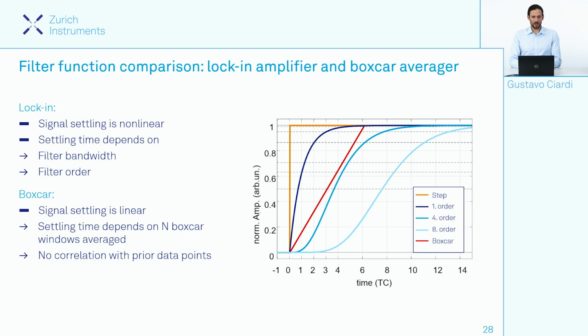Another very interesting and important difference between lock-in amplifiers and Boxcar Averagers is the filter function. For the lock-ins, the signal settling is nonlinear, exponential, and it depends on the filter bandwidth and the filter order. For Boxcar Averaging, instead, the settling is completely linear and only depends on the number of windows that we have averaged, and there is no correlation among prior data points.